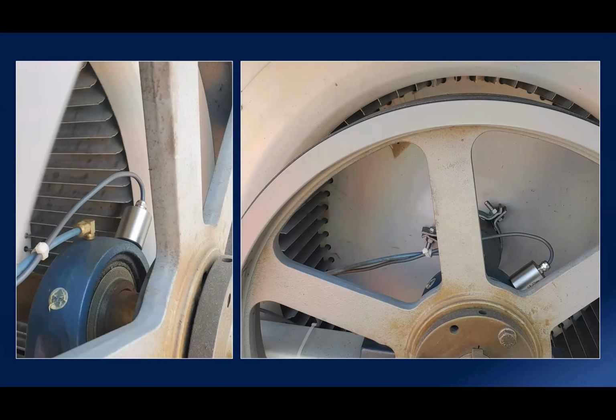And as you can see here, the cable itself is not in any conduit. It's not in any kind of seal tight or anything like that. So what we designed is this cable for outdoor applications to be run in cable tray, or in this example, be cable tied to the structure, this lubrication line. It is completely shielded from the tip of the sensor all the way back to the OnTrack. So even if it goes over top of high voltage equipment or other mechanical equipment, it is not going to pick up any other noise other than that bearing.